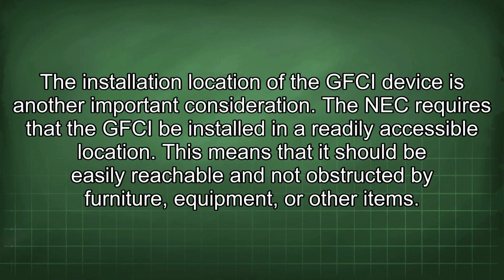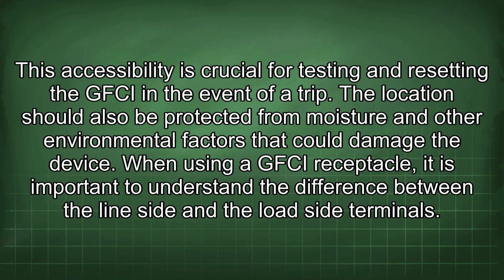The installation location of the GFCI device is another important consideration. The NEC requires that the GFCI be installed in a readily accessible location. This means that it should be easily reachable and not obstructed by furniture, equipment, or other items. This accessibility is crucial for testing and resetting the GFCI in the event of a trip. The location should also be protected from moisture and other environmental factors that could damage the device.